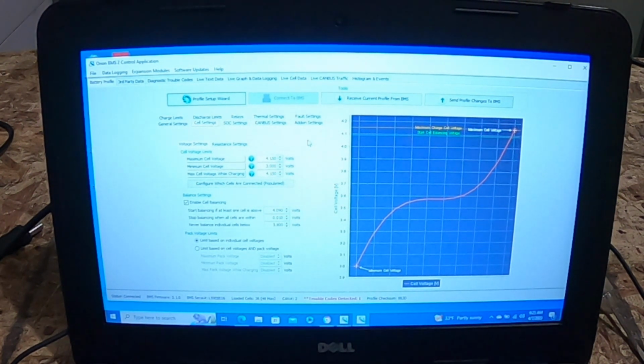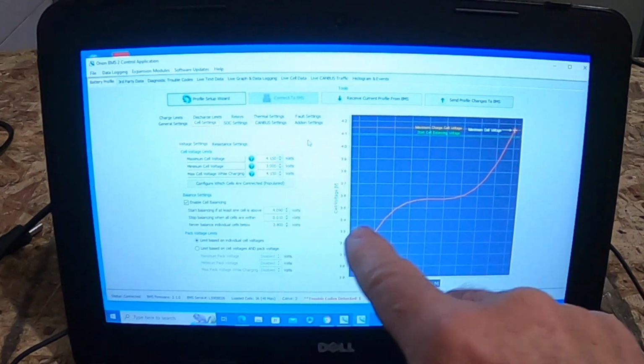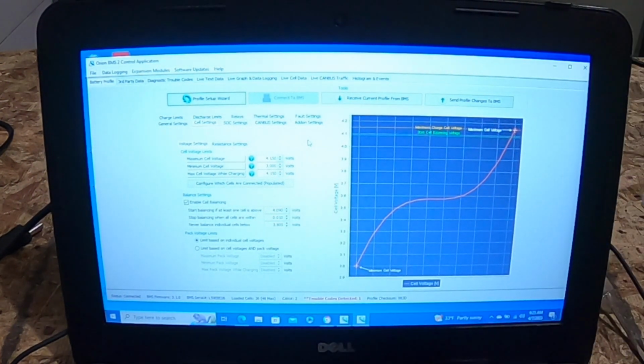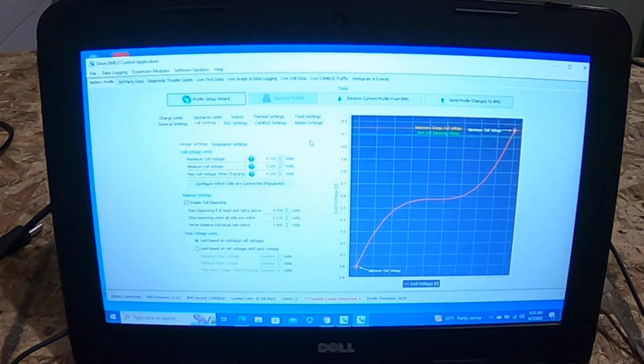And at the very end, once it hits about 85% as set up here, the current starts dropping off, maybe down to 5 amps, until it gets fully charged. So when you first plug it in, you don't want to hammer the batteries with full current, 28 amps at 6,600 watts coming in. You want to gradually ease into that, ramp up, hit them hard, and then at the end start tapering off until they're charged.